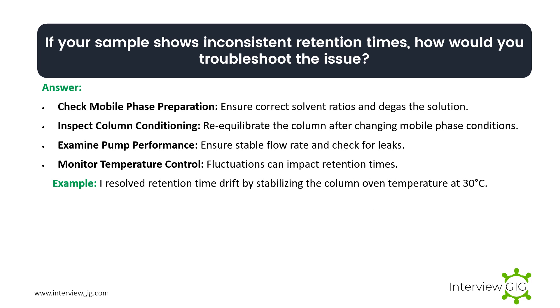If your sample shows inconsistent retention times, how would you troubleshoot the issue? Check mobile phase preparation — ensure correct solvent ratios and degas the solution. Inspect column conditioning — reequilibrate the column after changing mobile phase conditions. Examine pump performance — ensure stable flow rate and check for leaks. Monitor temperature control — fluctuations can impact retention times. Example: I resolve retention time drift by stabilizing the column oven temperature at 30°C.